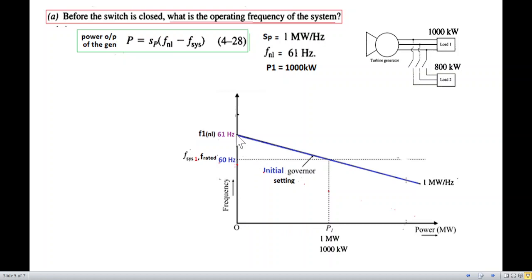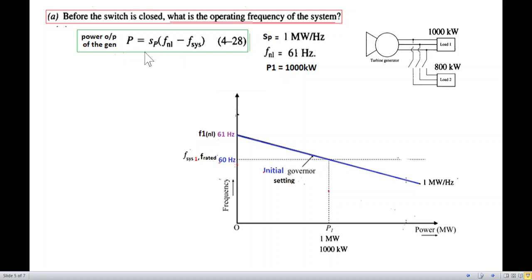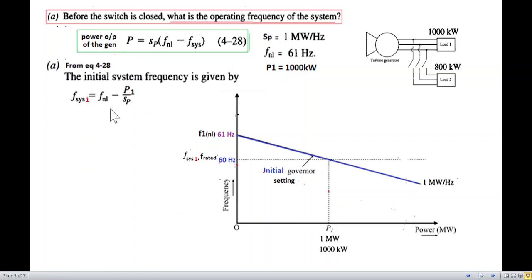We can see we have a no-load frequency of 61 Hz, and the load is 1000 kilowatts. The slope is 1 megawatt per hertz, meaning a 1 megawatt load drops the frequency by 1 Hz. To find the system frequency, we rearrange: f_sys = f_NL − P/SP = 61 − (1000 kW / 1 MW per Hz) = 61 − 1 = 60 Hz. So the operating frequency before the second load is connected is 60 Hz.